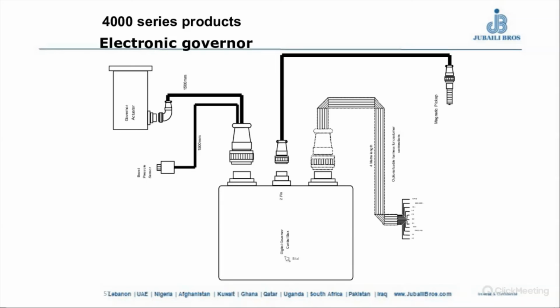Electrical connections: this is the controller again. What is connected to it? We have two sensors connected to these Heinzmann controllers, the digital type. We have a speed sensor connected to the controller so it knows the speed of the engine. For example, when load is applied, the engine speed drops. The Heinzmann controller knows the speed has dropped based on readings from the magnetic pickup, the speed sensor, so it gives orders to the actuator to move its arm to spray more fuel so the speed goes back up to 1500 RPM.